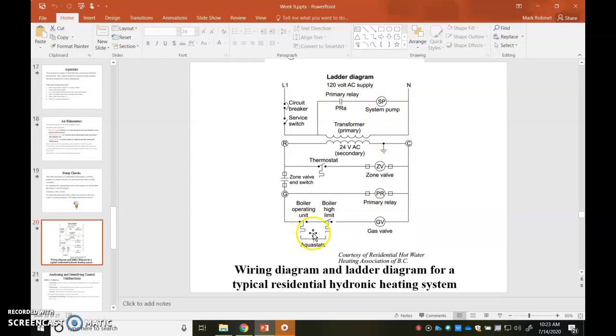And these two aquastats are normally closed. Right now they're shown in the open position. I have no idea why. But this boiler operating unit would be at 180 degrees. The boiler high limit is operating at 200 degrees, 20 degrees higher. So what you get is this. R comes through, the end valve, zone valve end switch is closed, goes through the two open switches and powers the gas valve. So now the water is being heating up.